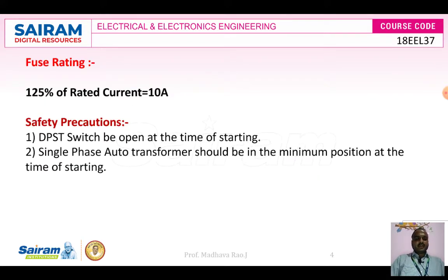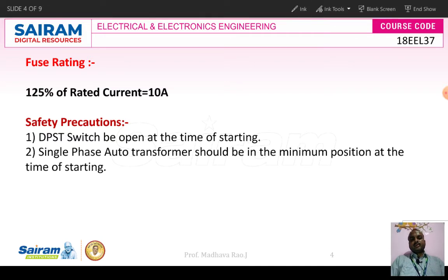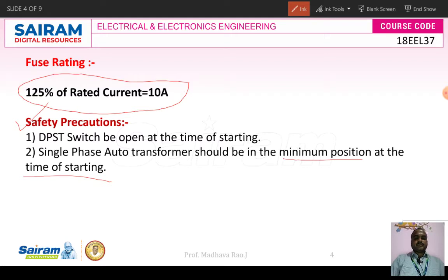So coming to the fuse rating, the fuse rating for the experiment is 125% of rated current, that is equal to 10 amperes. Since we are doing the experiment based on the load, we need 125% of rated current. So coming to the safety precautions. Before starting the experiment, the DPST switch should be open at the time of starting. Next, the single phase auto transformer should be in minimum position at the time of starting. These are the two precautions we have to take before conducting the experiment.